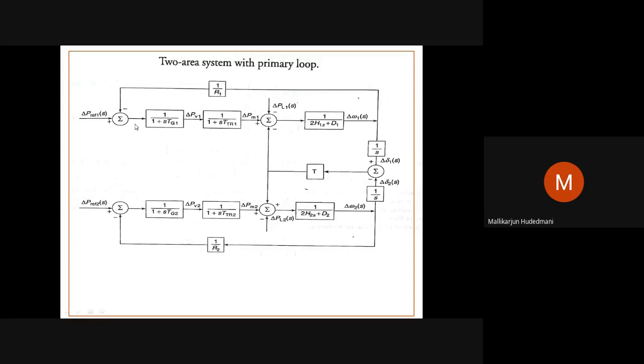The governor will transform this frequency deviation error to displacement of the valve to be opened or closed. That is nothing but the output of the governor block. Then the governor block output delta PV1, say, will make the turbine accelerate. If there is a deviation, a shift of frequency, meaning a frequency drop is noticed, then what is to be done?